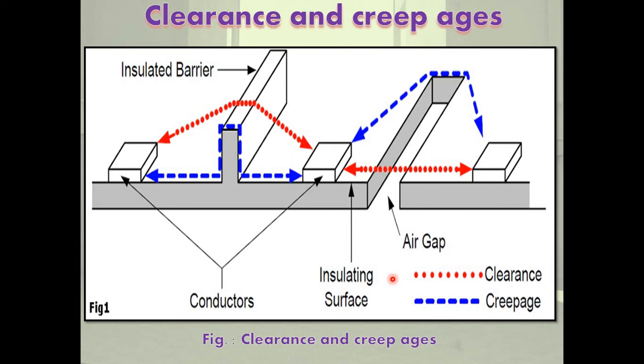Clearance means the clear minimum distance between two conducting points separated by air or gas or oil. Clearance should be more than the minimum flashover distance. The person moving in the insulation and working on dead or earthed equipment or structure should not come in the work section. Clearance should be adequate for maintenance of plant and equipment. Clearances are very closely associated with electrical safety design. Minimum phase to ground clearance, phase to phase clearance, ground clearance, isolating clearance, safety clearance, etc. are specified in Indian standards, Indian safety rules and various design specifications of electrical plants and equipment. Safety engineer, design engineer and electrical inspector ensure that adequate clearances are provided.